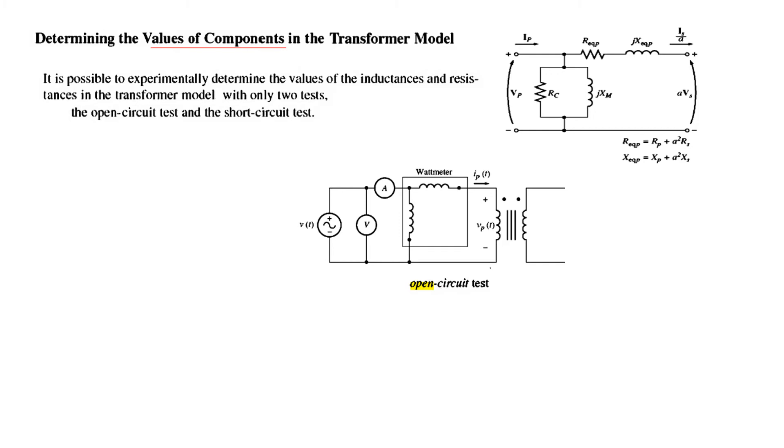In the open circuit test, we do not connect any load at the secondary side. And we have connected an ampere meter and a volt meter here. So we measure the current and the voltage. And you can see, with this, we'll be able to find out the parallel components. So Rc and Xm can be calculated by this method. And since they are in parallel, we can write them to be as an admittance Ye, which is equal to one over Rc minus J over Xm.